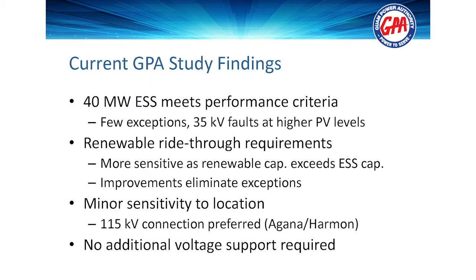In the GPA system, like most islanded systems, you have to put up with more things that a utility on the mainland does not. One of the things that happens is that on the mainland, when you have a fault on your transmission system, and by a fault we mean a tree falling in the line or the line falling on the ground, the frequency stays constant at 60 hertz, right? Your voltage may change, but your frequency stays constant. In an islanded system, that's nothing but a dream. So when you have faults in your transmission system, you have a big swing in voltage and a huge swing in frequency. And this battery cannot handle all of the swings in frequency and voltage on the GPA system. There are a few cases where it doesn't.